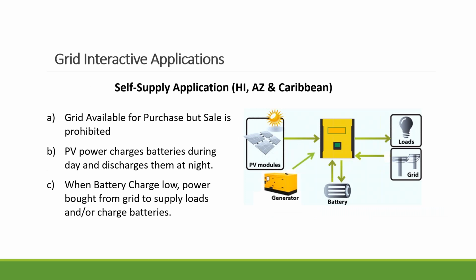If you are living in Hawaii, Arizona, or the Caribbean, you do have access to the power. However, either the grid power is very, very expensive and the quality is very poor, or you don't have net metering. So basically, you cannot feed the PV power back to the grid at all. In that case, adding a battery totally makes sense, because you can capture the excess power during the day and then discharge the battery in the evening. And you can still use the grid basically as a second source. If, for instance, in the evening the battery has been discharged to a low percentage, then the grid can kick on, start supplying the home, and charge the battery. So those are the commonly seen applications.